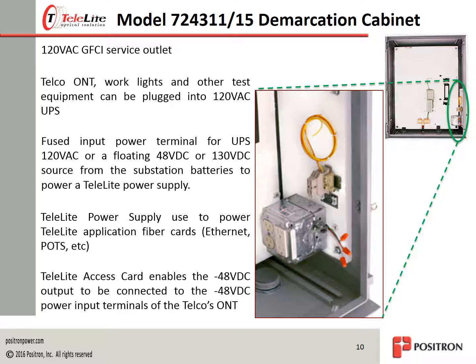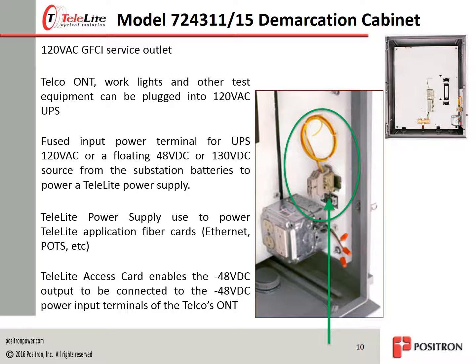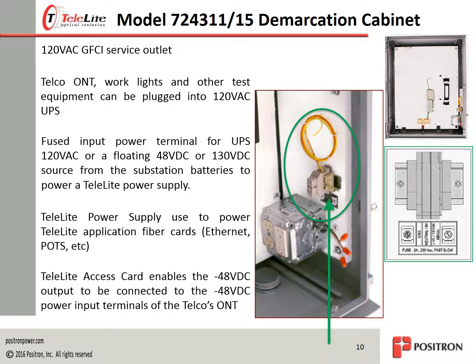A convenient power panel is installed in the lower right-hand side of the DMARC cabinet. An uninterruptible power supply, or UPS, can be installed to deliver service AC to the 4 receptacle GFCI power outlets. The telco can plug the ONT into the 120-volt service outlet, or, if a TeleLite optical system is used to continue the circuit transport into the control house, 120V AC, floating 48 volts DC, or floating 130 volts DC can be fed in via the fused input power terminal block.